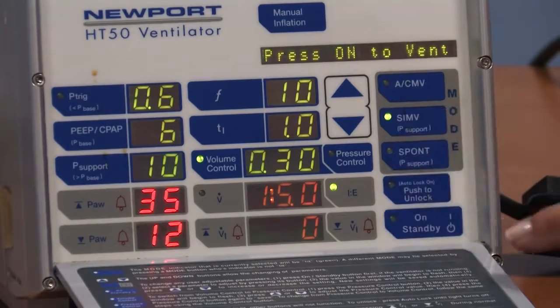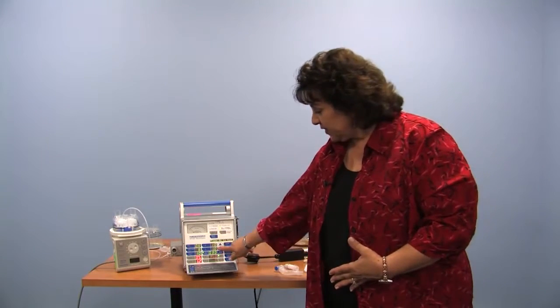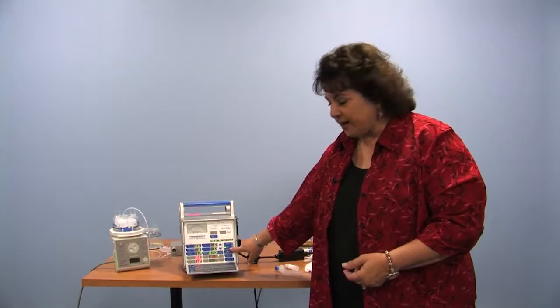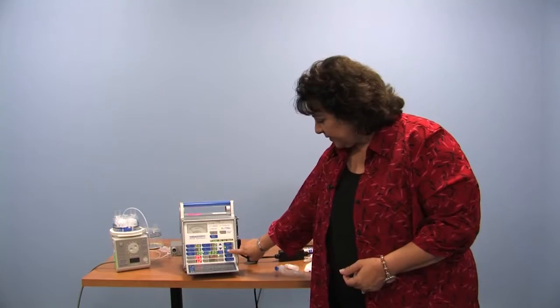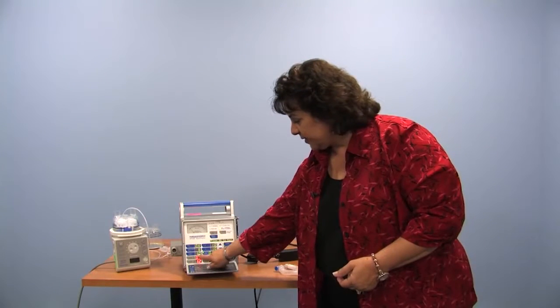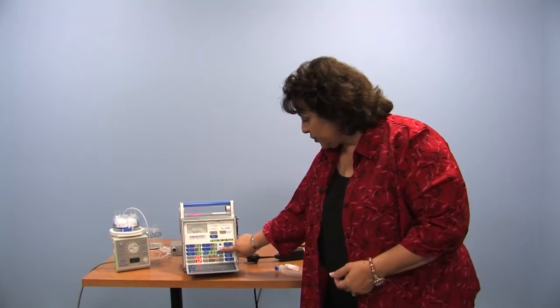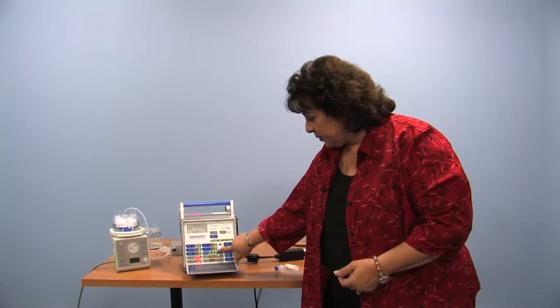The most common mode is SIMV, synchronized intermittent mandatory ventilation. It means that those 10 breaths are going to come approximately every 6 seconds, but we want your child to be able to ask for it and turn it on and have it blow in when they're breathing in, not just fire by the clock. So if they're sound asleep, deep sleep, or just had some medication, it will fire every 6 seconds. But if they take a breath, it will deliver it during their inhale effort and make it more synchronous with their breathing effort. That's where the S comes from. And as it says here, this could have pressure support with it, like it does now, the 10, or we could touch this button and turn this off if we wanted to. So we have a choice.